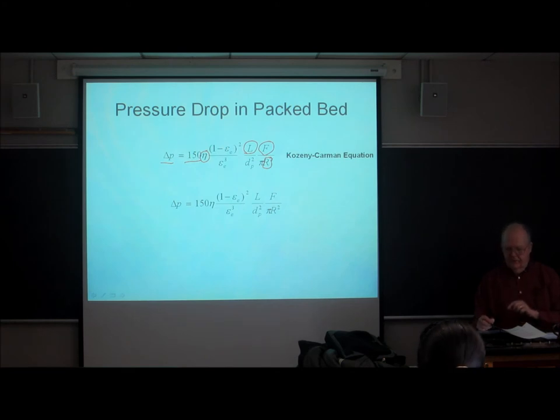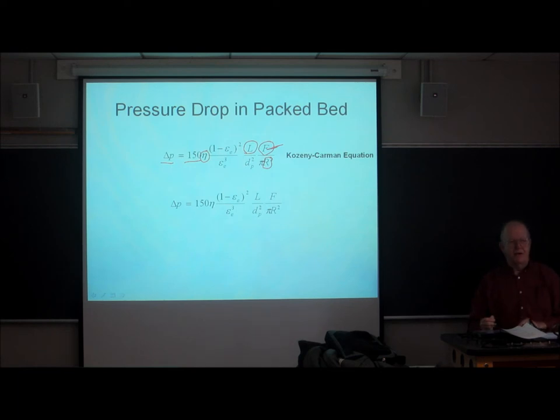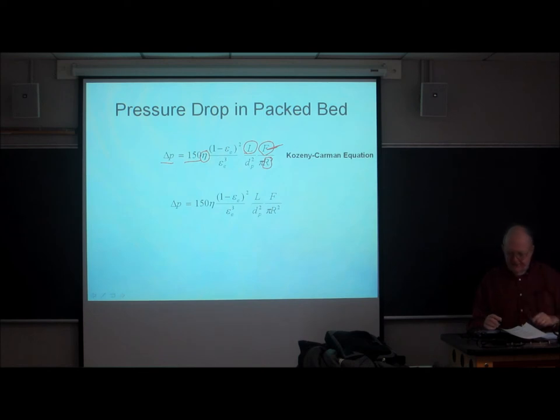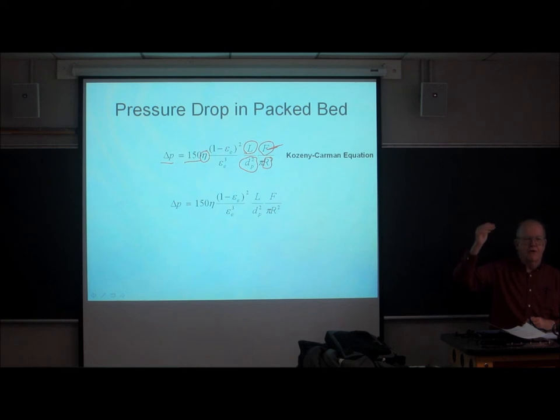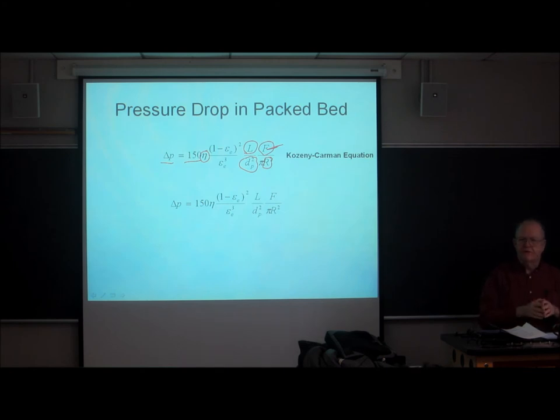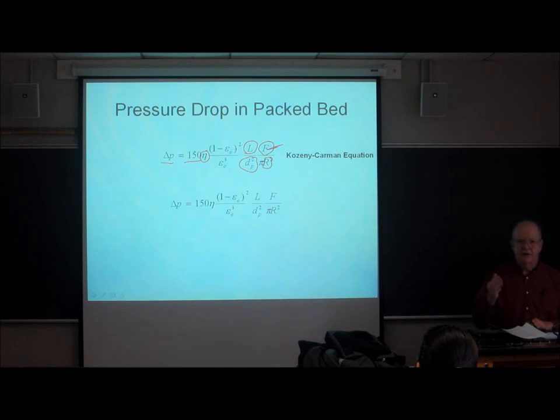If we put linear velocity instead of flow rate, the radius dependence cancels — what really matters is the linear velocity, not the flow rate. And here's the key: pressure depends inversely on the square of the particle diameter. Over the history of LC, particles have gotten smaller and smaller, and every time the particle diameter drops by a factor of two, the pressure drop needed goes up by a factor of four. This accounts for the increase from 400 bar to 1,200 bar over the past few years.